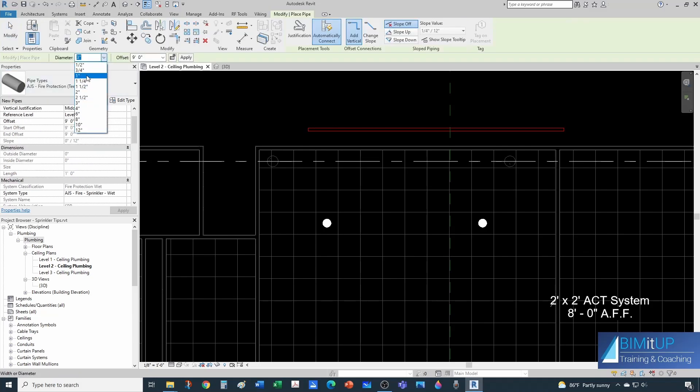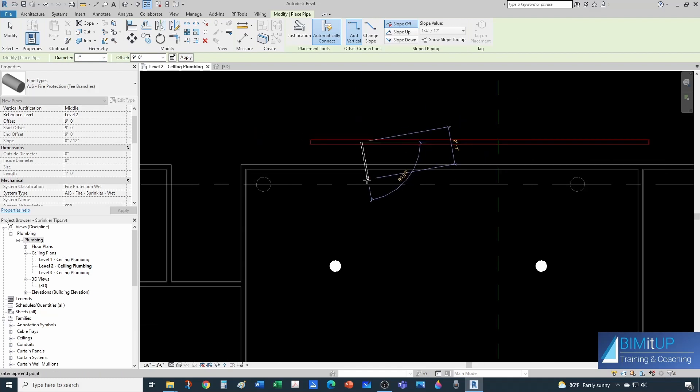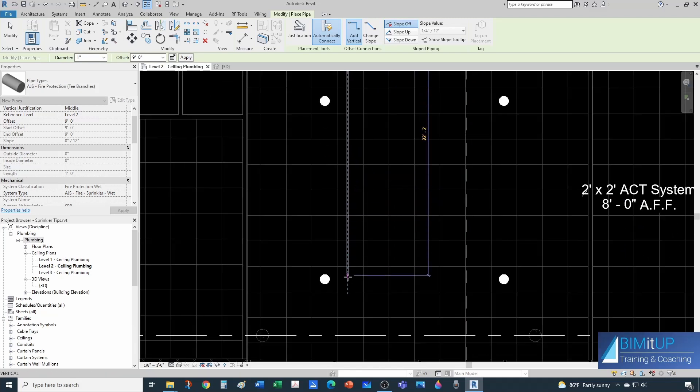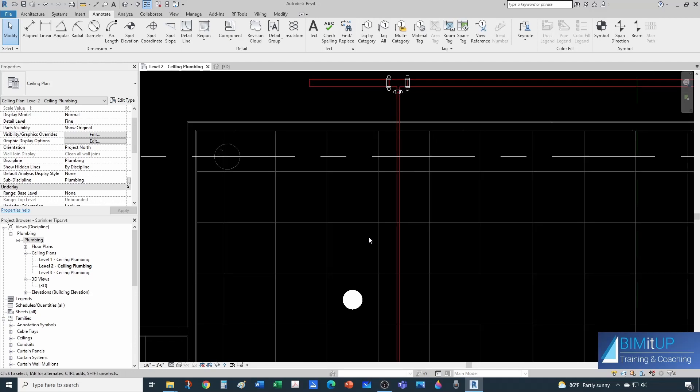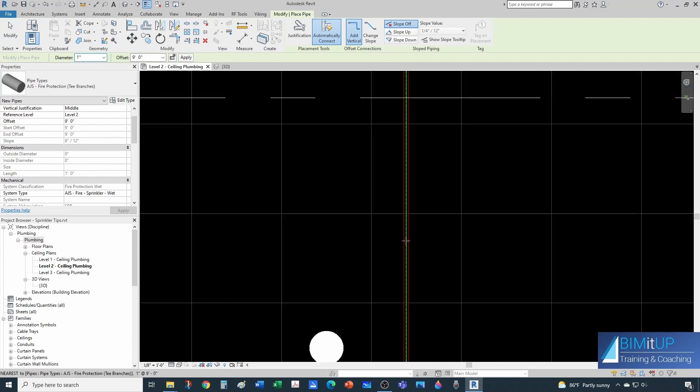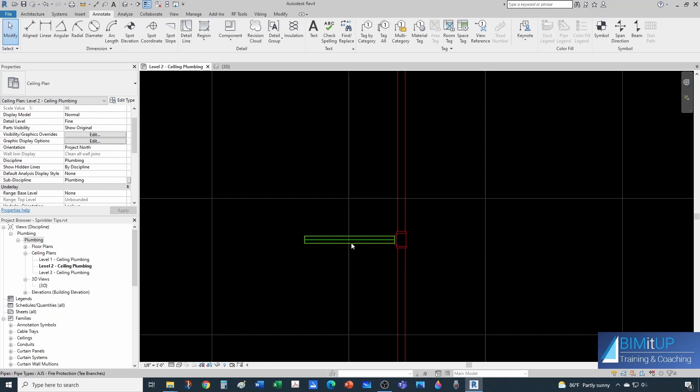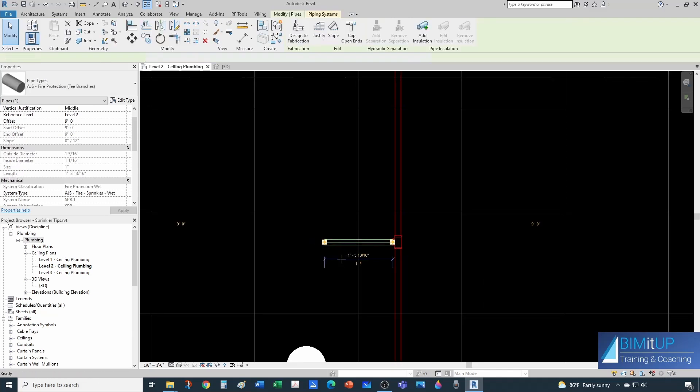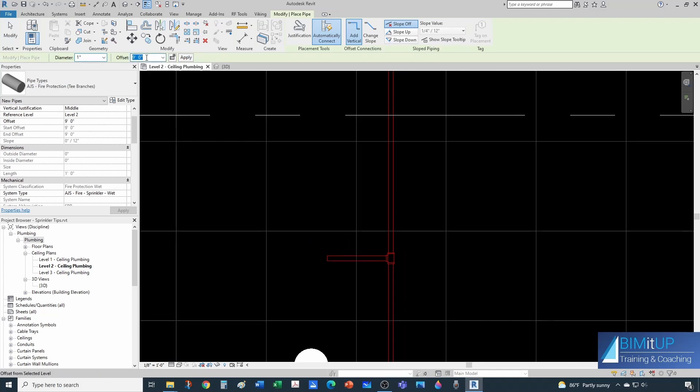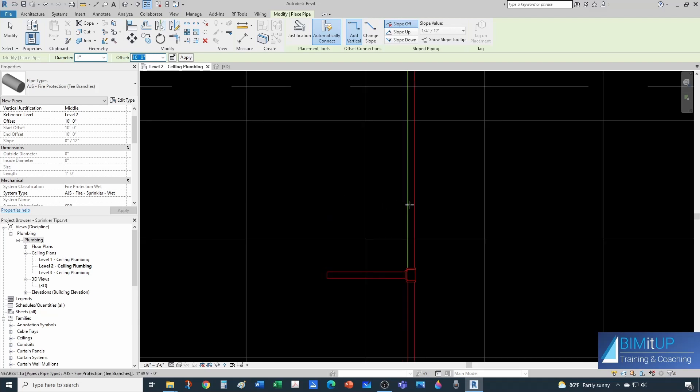I'm gonna keep it at 1 inch and I'm coming out of here with a grooved fitting. I'm gonna go all the way here. One of the things that frustrates people a lot is that if I do PI for piping and I want to snap to this pipe, I get a perfectly horizontal connection with my branch, and that's what people are used to. Now if you were to do the same thing but instead of being at 9 feet you were at 10 feet, AutoCAD users and our intuition would tell us that if this gets highlighted it's gonna connect to that pipe. That's still true, but the way Revit thinks about it is that if you have this elevation and you have Add Vertical on, it's gonna introduce a riser.